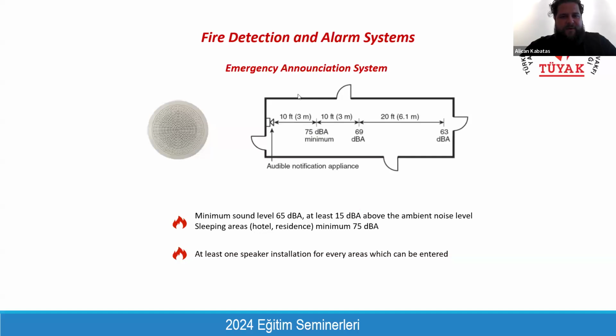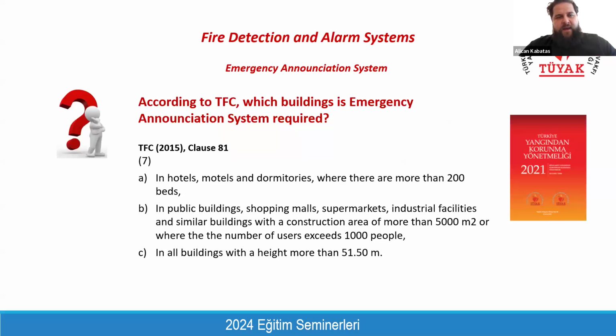And we will have an emergency announcement system. These are the speakers, and it is called public announce and voice alarm system. And we have some minimum sound level requirements. That's why we should have at least one speaker at every room. It means locating speakers only at the common corridors or common areas will not solve the issue. We need to have speakers within every room, and the ceiling design and the ceiling coordination should be done accordingly.